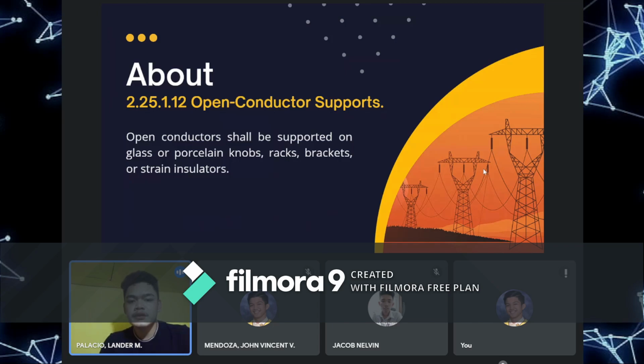So about 2.25.1.12, open conductor supports. It says here that the open conductor shall be supported by either glass or porcelain knobs, racks, brackets, or strain insulator. So yung mga open conductor support natin. Pag sinabing open conductor support, open nga. So it shall be supported daw po, no? By glass or porcelain knobs, racks, or brackets, or strain insulators.